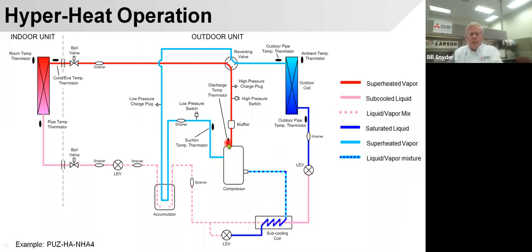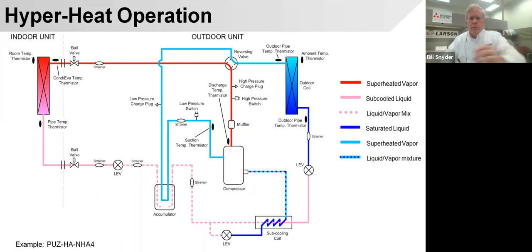First thing you see here is this little black dot, a discharge temperature thermistor, because we're monitoring the discharge temperature coming off that compressor. There's a high pressure switch and charging plug in there. We go through the reversing valve. You'll notice there's a strainer here. Mitsubishi has lots of strainers in their equipment, so just be aware that there are strainers there that will pick up any junk that might be in the system. They could plug if there's a lot of stuff in the system.